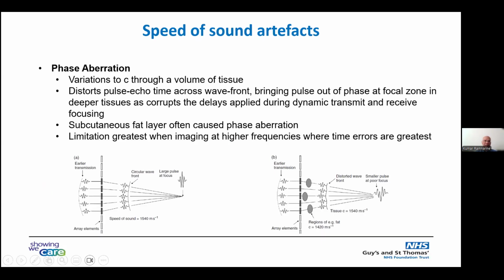So this is highlighting the distortion, the defocusing that you can get if you have interfaces within the path that result in different speeds of sound. Then the wavefront at the focus will be distorted, and that will reduce the image quality.